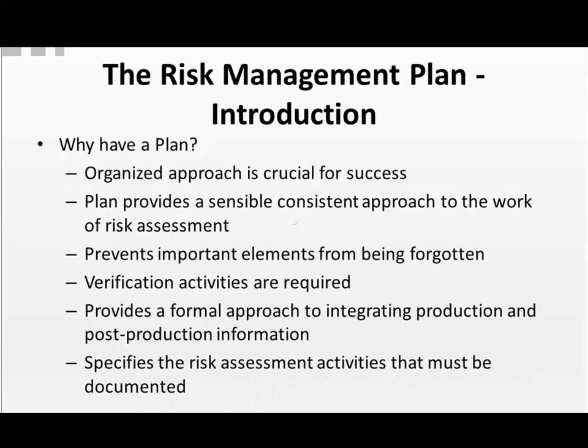Now, as we continue talking about this risk management plan, why is it that you think we should have one? Well, the risk management plan really is an organized approach. It's crucial for success. The plan provides a sensible, consistent approach to the risk assessment. Risk assessment activities really must be planned and documented. It prevents important elements from being forgotten, especially as we move into the life cycle of the device, and how the life cycle of the device will certainly or possibly may alter risk.